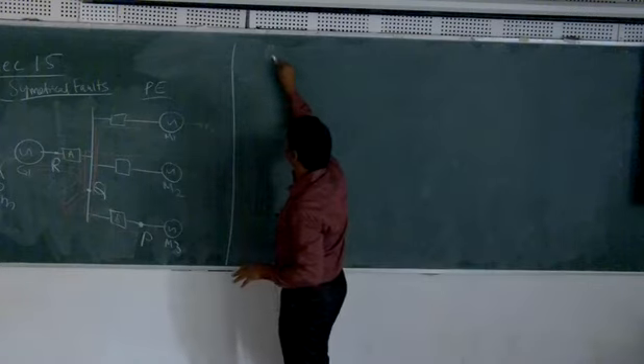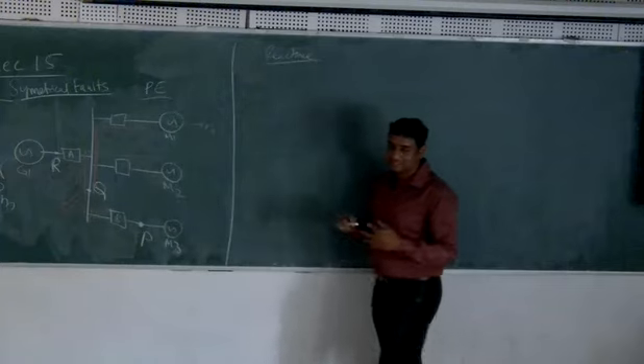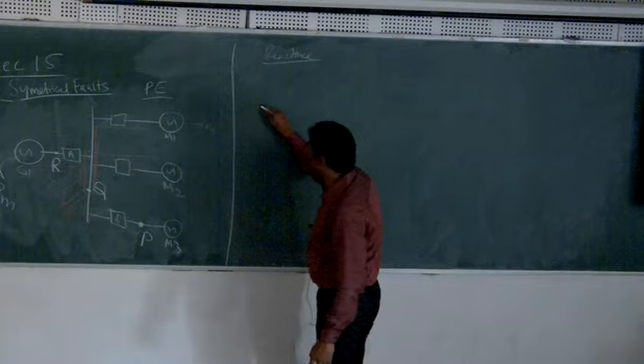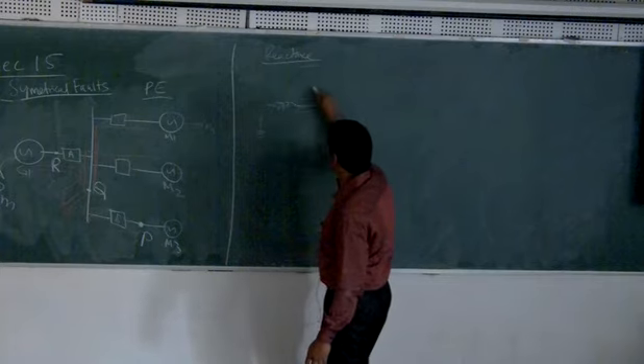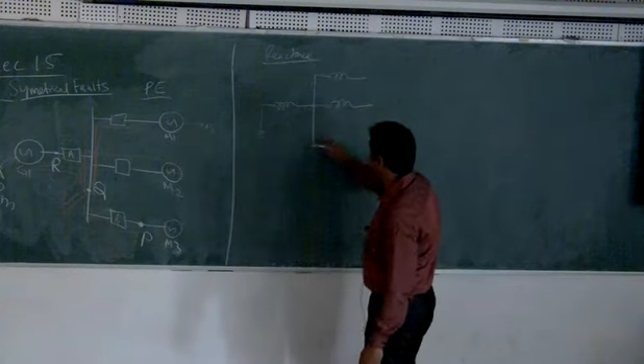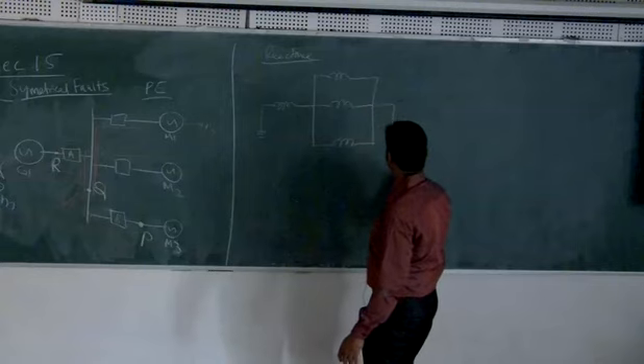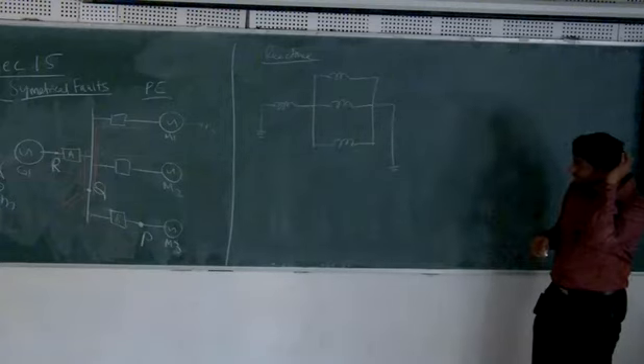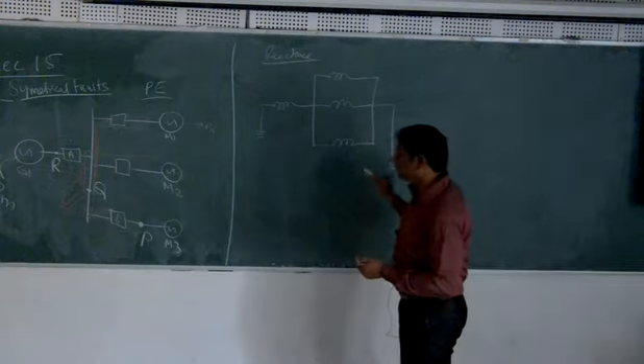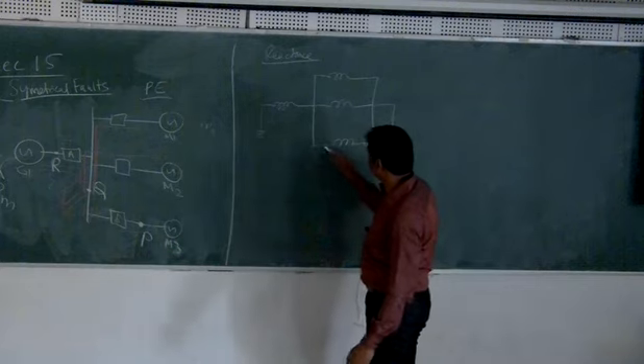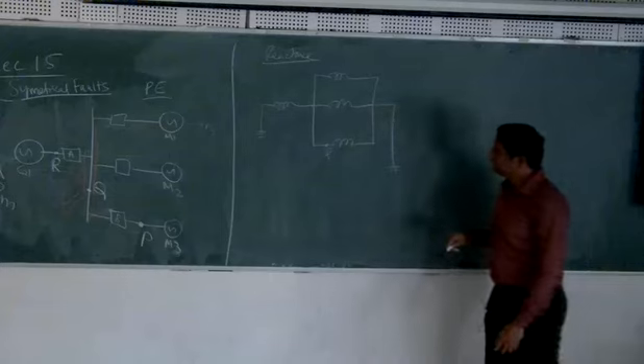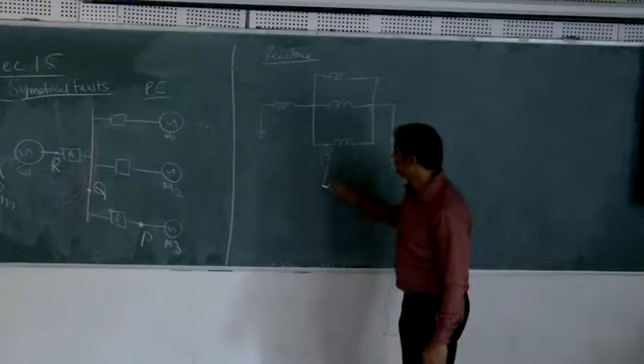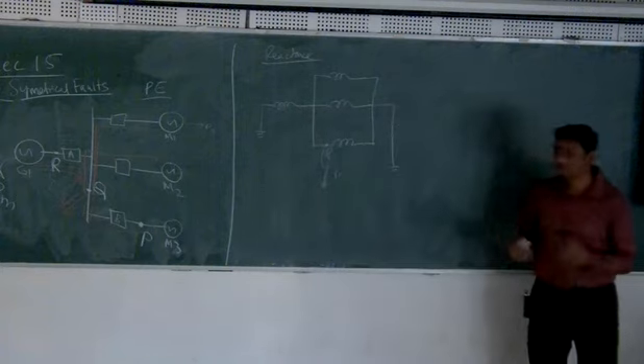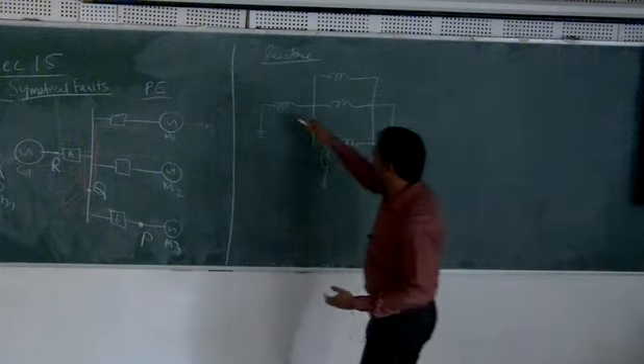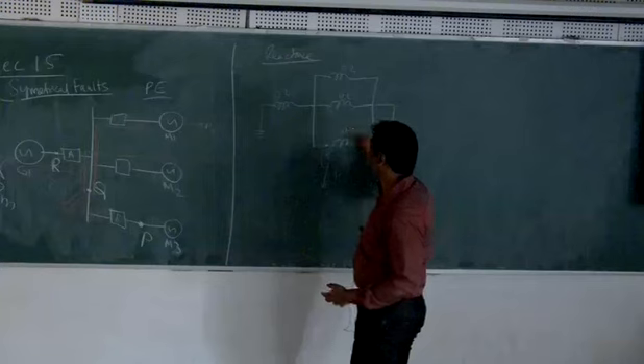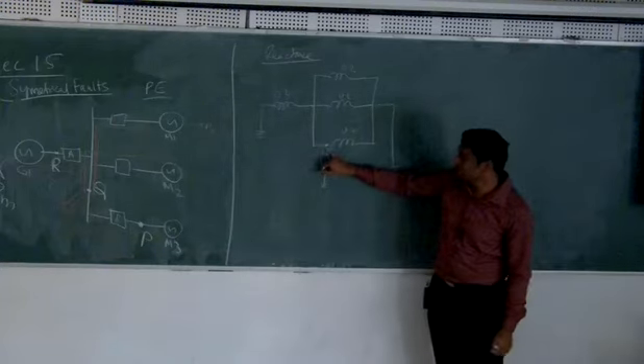So if I go for reactance, for the fault calculations part, the reactance diagram will look something like this. The machine is short circuited, and then there is one reactance, another reactance, another reactance, another reactance, and these three are also short circuited. And if there is a fault, this fault P, the point P is located somewhere here. Then the question is how much is the fault current? You have to find the Thevenin's equivalent impedance. Let's say this value is given as 0.2, 0.2, 0.2, 0.2. I'm not writing it here. So what is the Thevenin's impedance at this point?